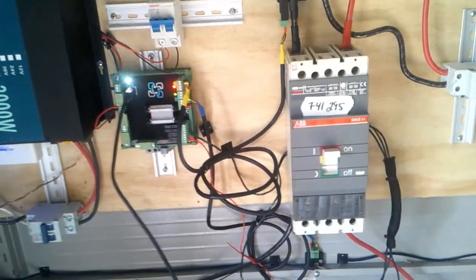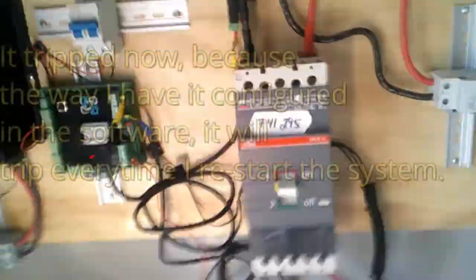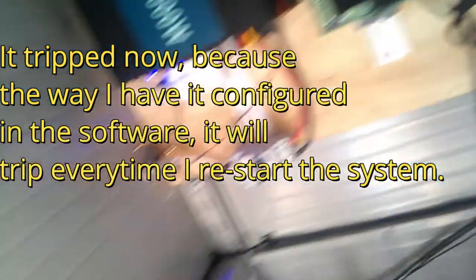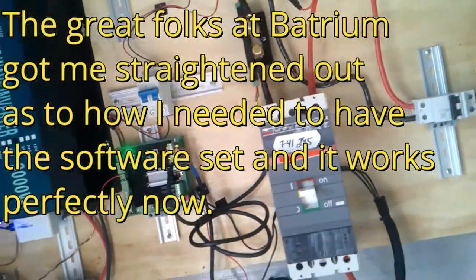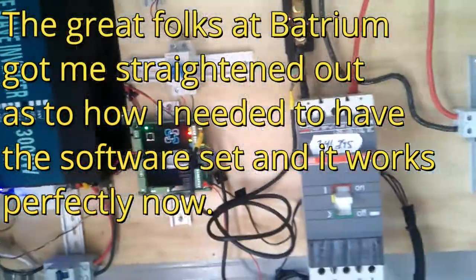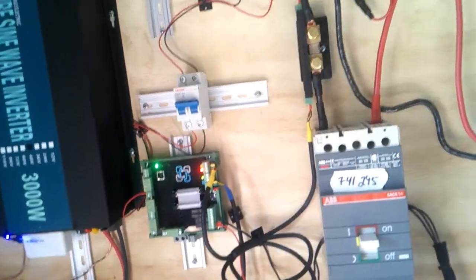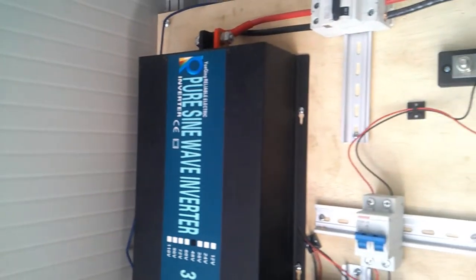All right, so what's the problem? The problem is everything's working. Why did it trip? Did it trip? I don't think it tripped. The problem is everything's working perfectly. So what does that mean? The relay is working fine, it's shutting off the battery. The problem is there's enough solar energy coming in from the solar system to keep the Batrium powered and to keep the inverter powered.